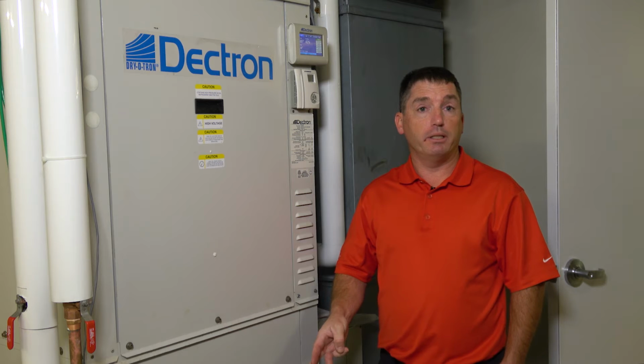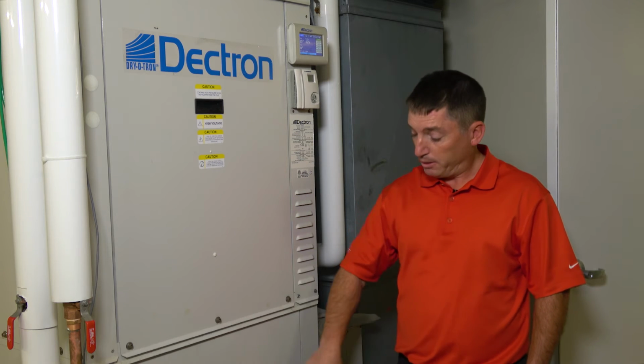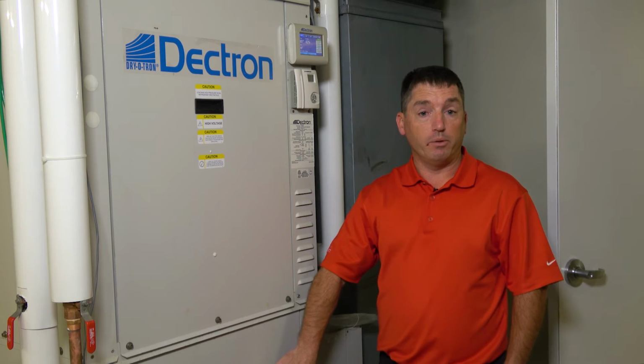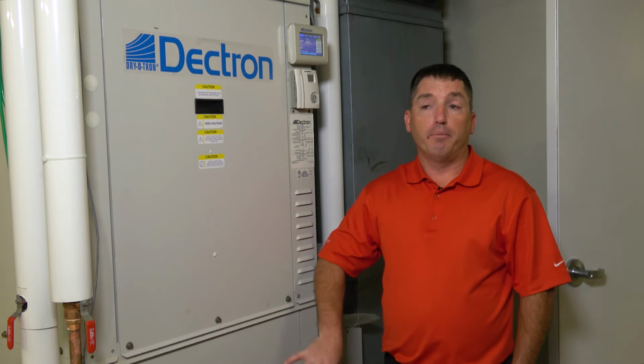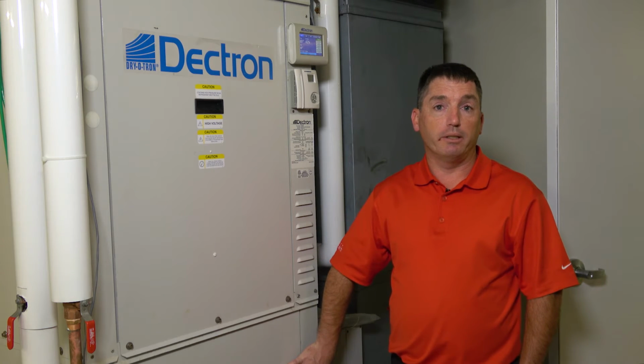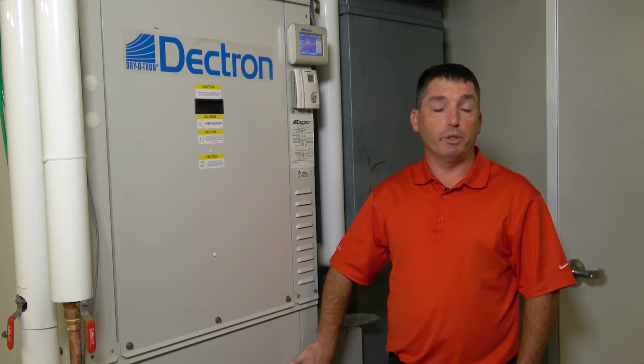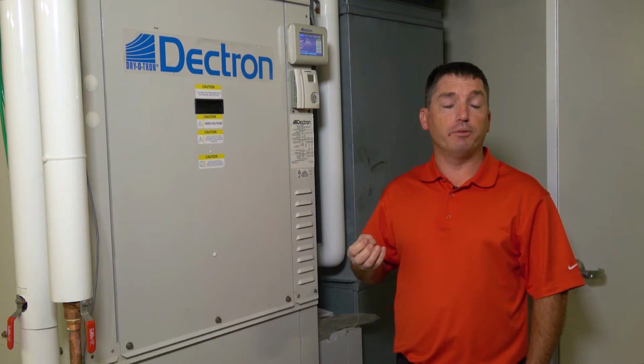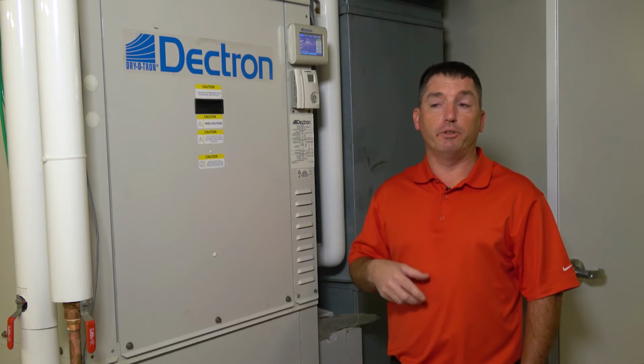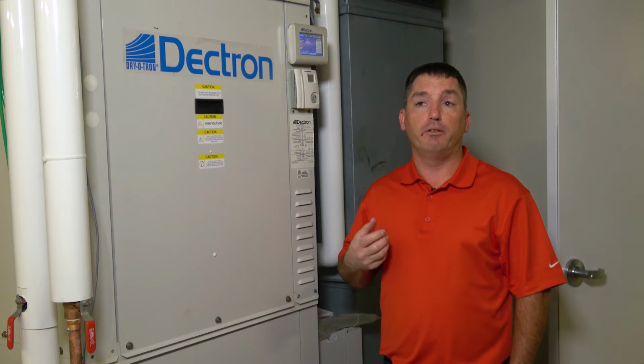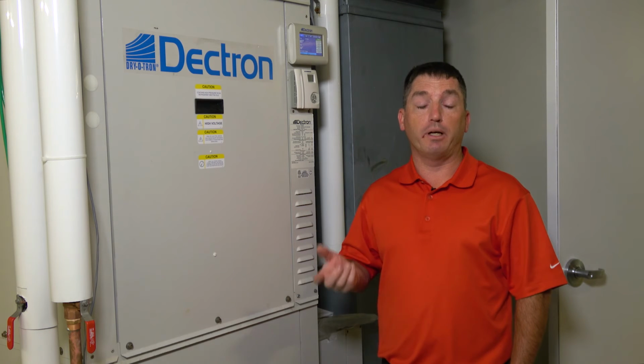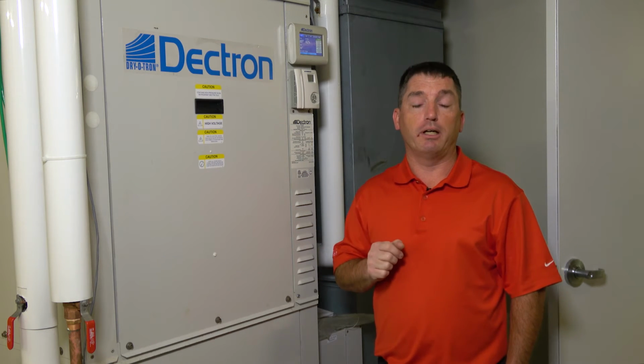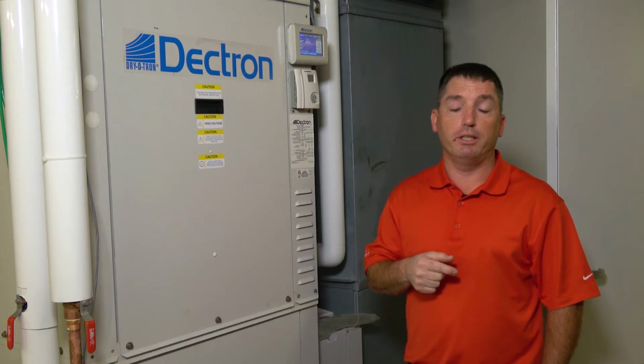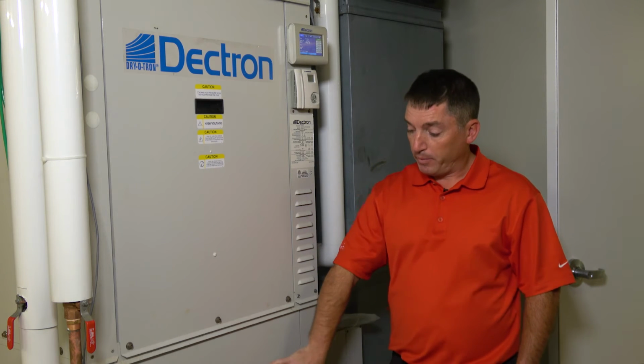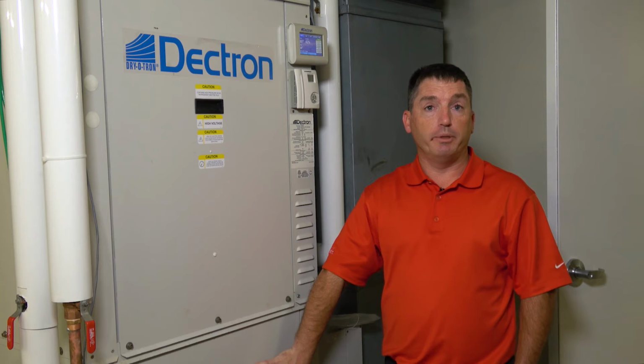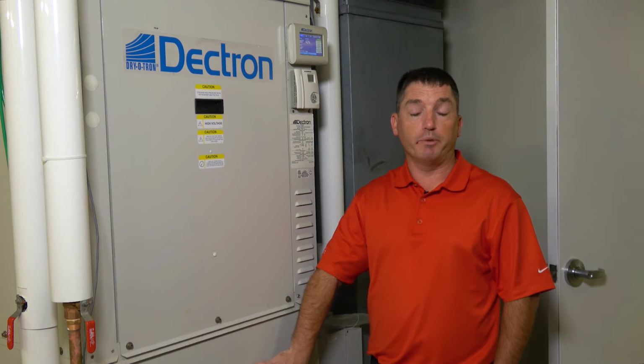Then we have 3 heat sinks that we can use. One is an air reheat coil. Because we've cooled the air in order to wring the moisture out of it, we have to reheat that air before we introduce it back into the space. If we were to introduce it directly without reheating it, you would basically have a rainforest in the pool area. So we're always going to be reheating the air to a certain point when we're dehumidifying.